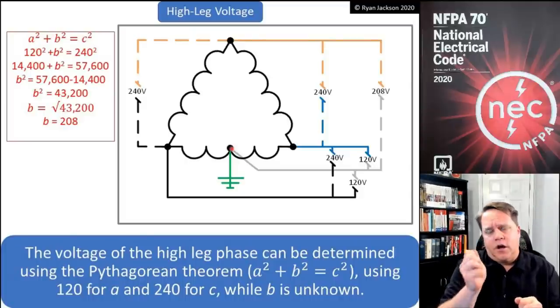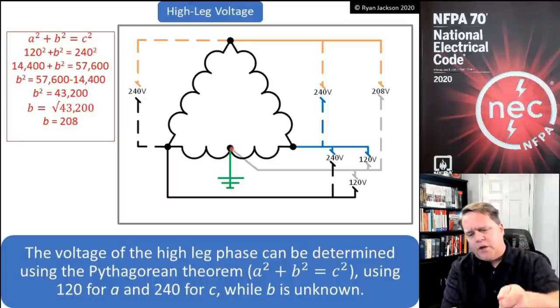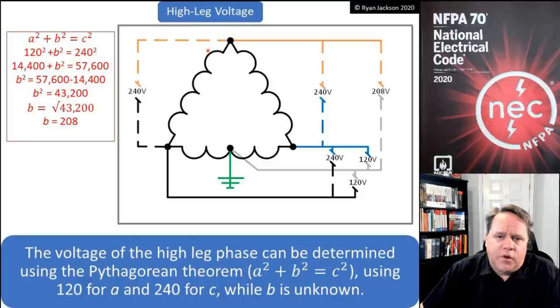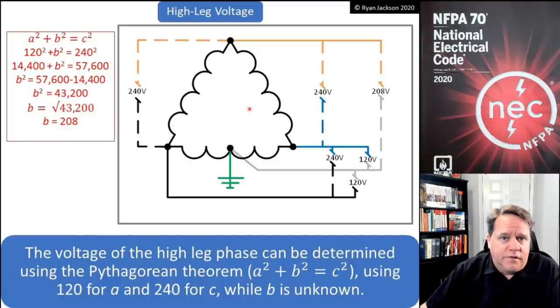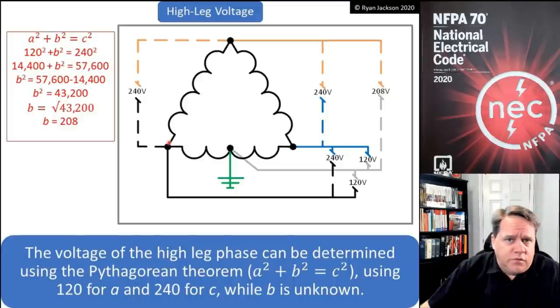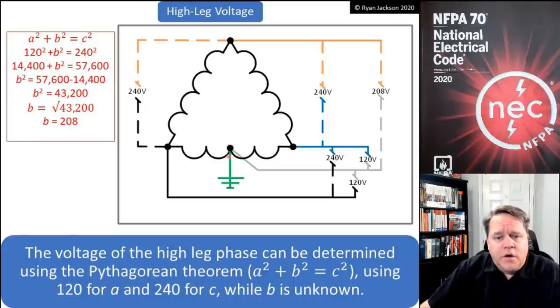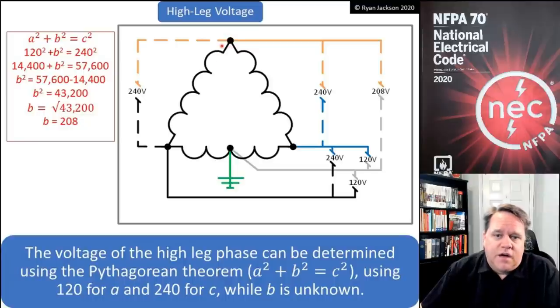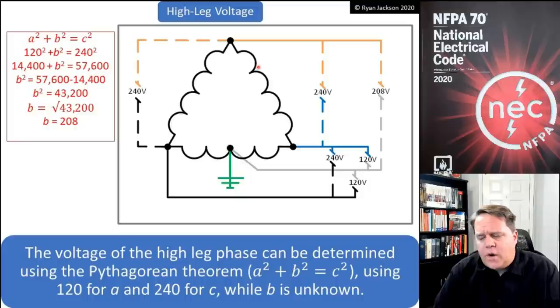If I take my meter and connect it to the neutral and read voltage to one line I'm going to get 120; I'm also going to get 120 to a different line. But what voltage would I get from the opposite point up at the top? That point is what we call the high leg, and the reason we call it the high leg is because you're going to get 208 volts. We figure this out using the Pythagorean theorem — a² + b² = c². We use 120 volts for A, we're solving for B, and we use 240 volts for C (the hypotenuse), and the math yields 208 volts to the high leg phase.